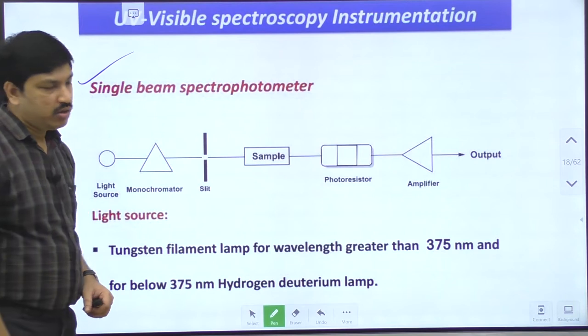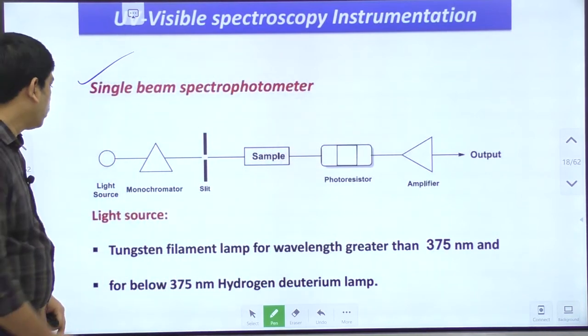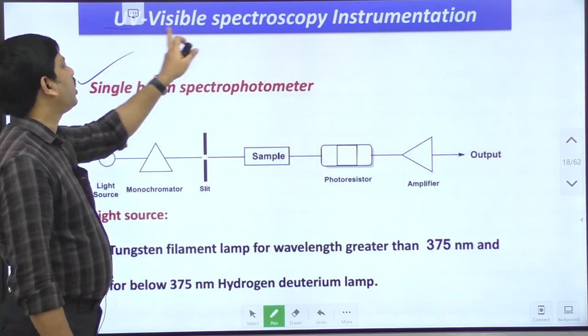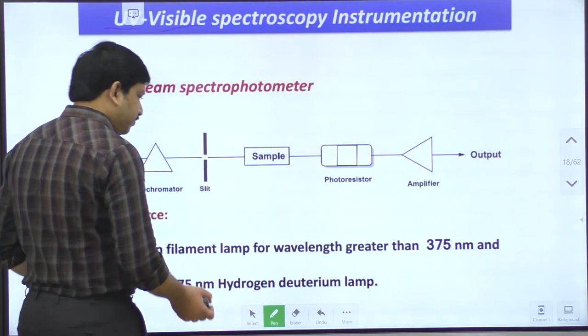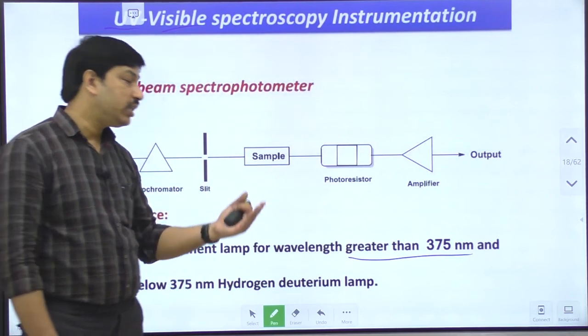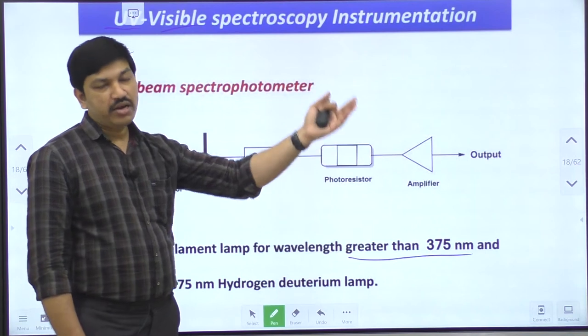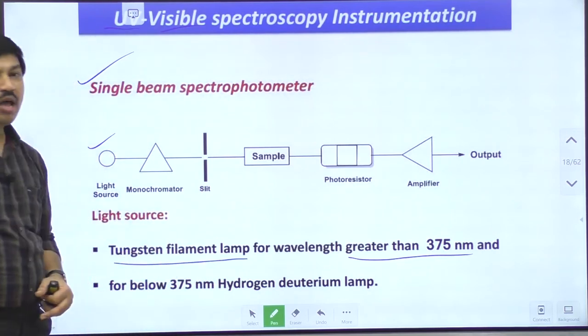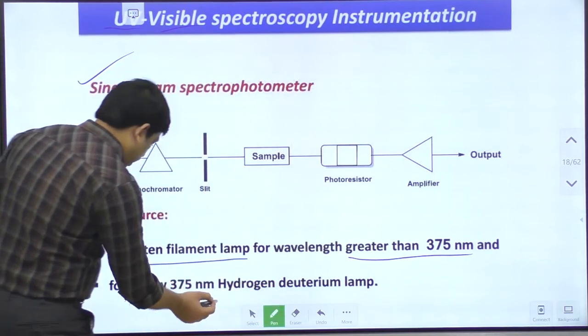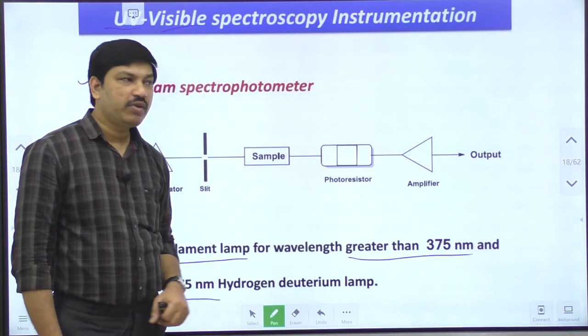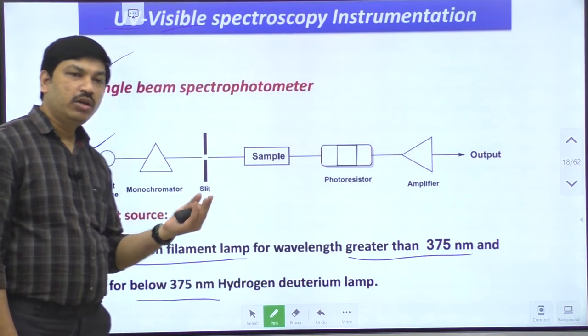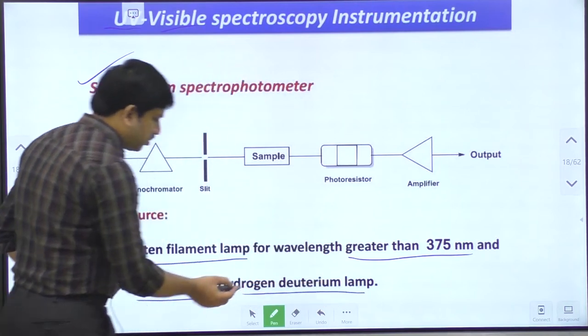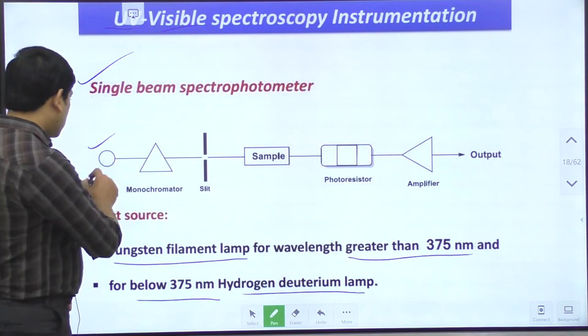This is the block diagram of the single beam spectrophotometer. The first component is the light source. In UV-visible spectroscopy we have two types of radiation — UV radiation and visible radiation. To generate wavelengths greater than 375 nanometers, meaning visible light such as 400, 500, or 600 nm, we use a tungsten filament lamp. To generate wavelengths less than 375 nanometers, such as 200, 220, or 320 nm, meaning UV radiation, we use a hydrogen or deuterium lamp as the source.